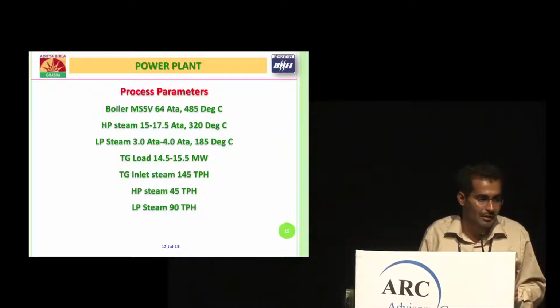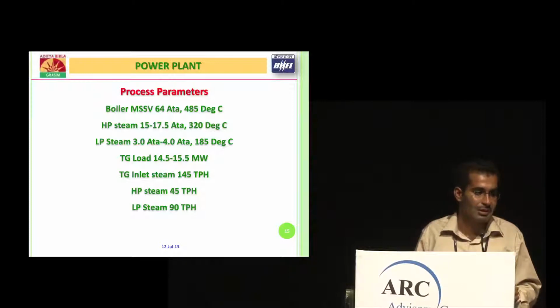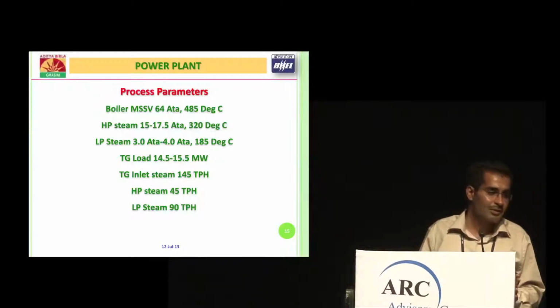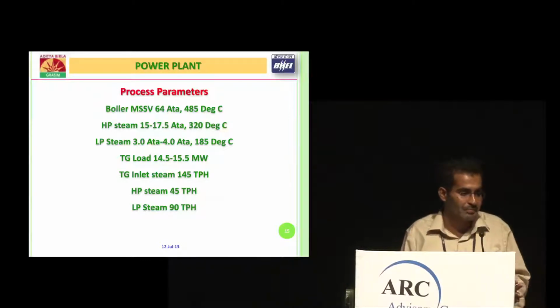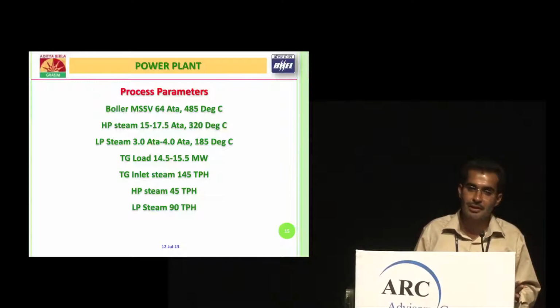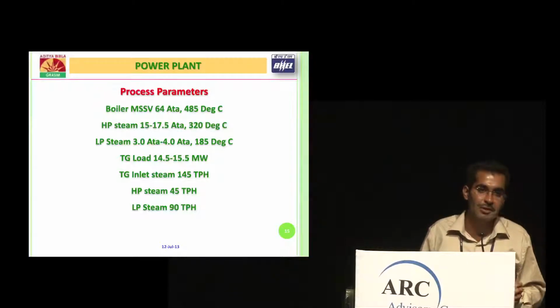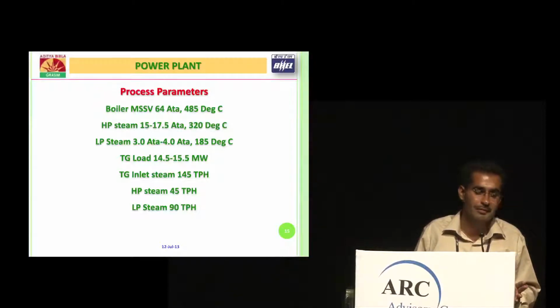So HP steam we are extracting through a controlled extraction. The pressure ranges from 15 to 17.5 ATA. Of course, this is controlled by the governor. And LP steam varies between 3 ATA and 4 ATA. Again, this is also a controlled extraction, controlled again by the governor. And the turbine load varies between 14.5 to 15.5.